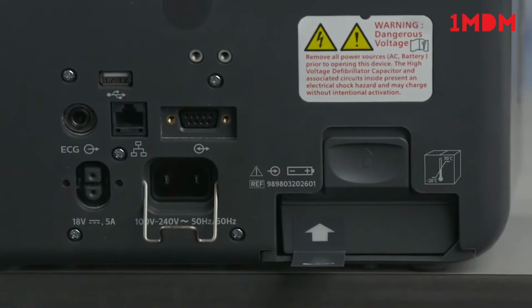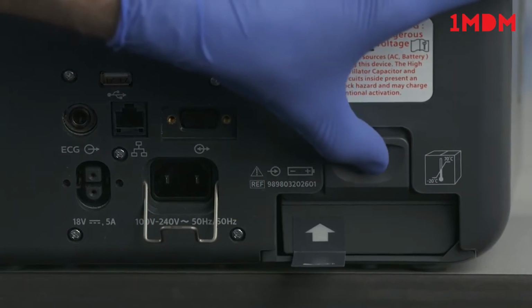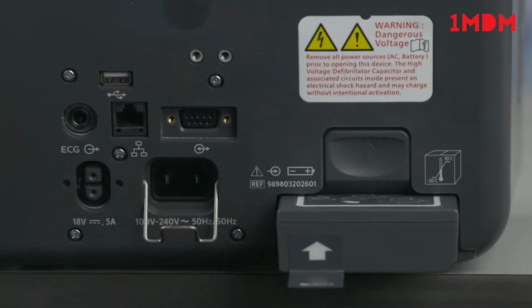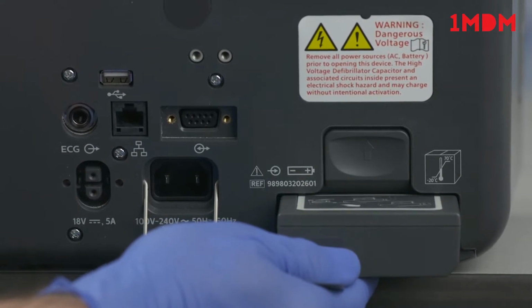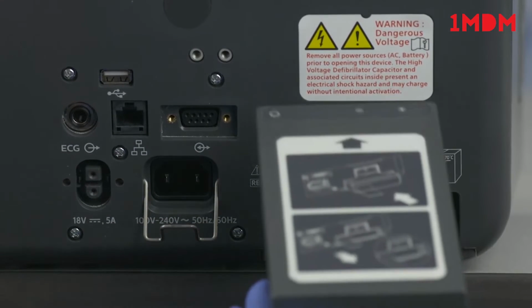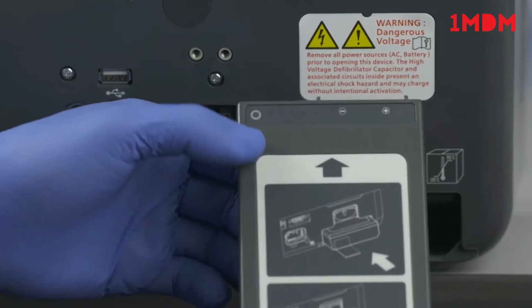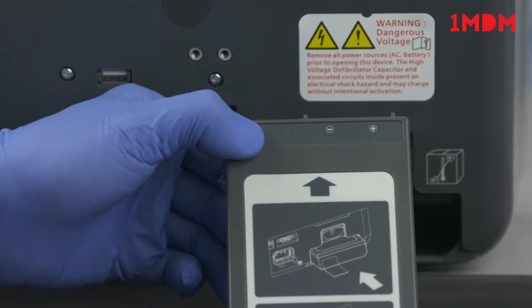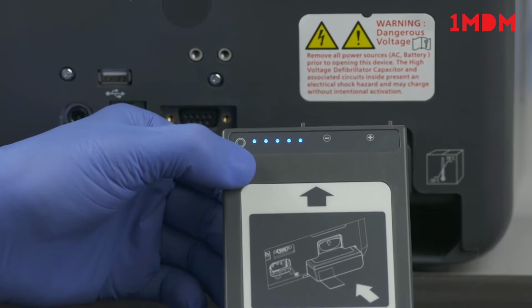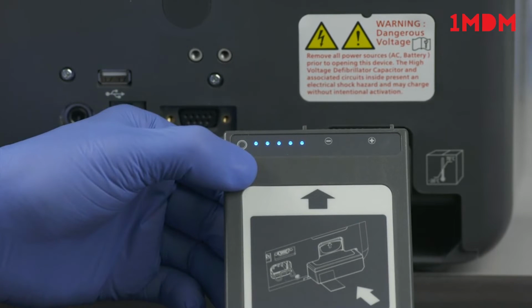Here, on the back of the device, is the battery compartment, which houses a rechargeable lithium-ion battery. The HeartStart Intrepid battery has a battery power gauge located at the end of the battery opposite the battery tab. Each solid blue light indicates approximately 20% charge. A flashing blue light, farthest from the button, indicates the battery is too weak to operate the device and must be recharged before use.